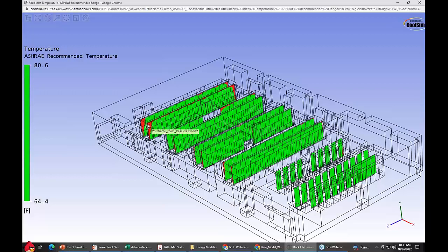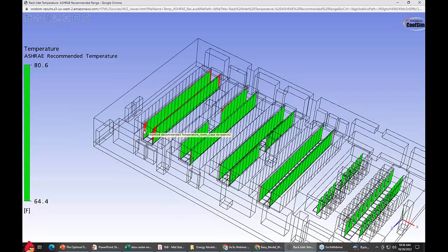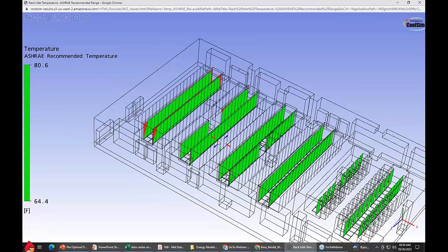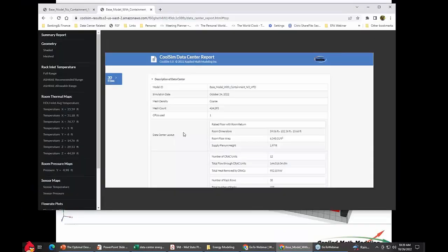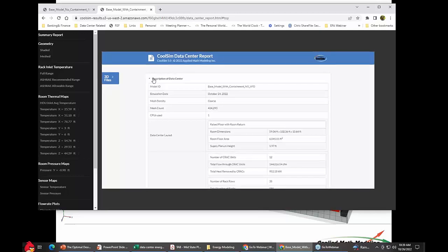By the way, these corners generally don't matter too much. It's not like you're going to stick high-density servers up there. If you're experienced, you tend to be sensitive about the ends of an aisle anyway. So this one's probably fine in terms of operation. And you notice here we're operating at a supply temp that's higher as well.